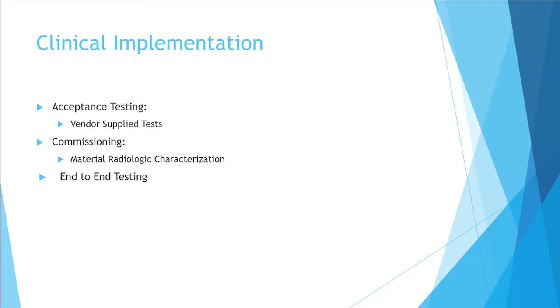Okay, so the first part of that process, as I mentioned, was acceptance testing, and there were three main areas that we checked during this. So Adaptiiv provided us with a STL file of this part that you see at the top. In yellow is the design dimensions of it, and that picture of the blue is the printed part that we printed to test it, that is printed in PLA. So the first part is testing the geometric accuracy. So the part has all these known dimensions, and you measure it along all these axes to make sure that it's dimensionally accurate within 1 millimeter. And so we found excellent agreement with that.